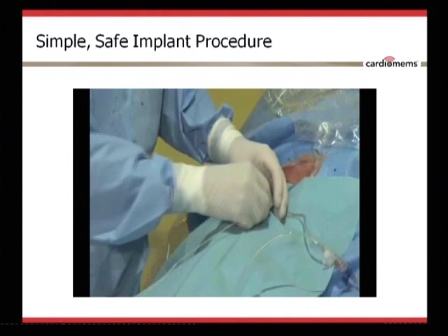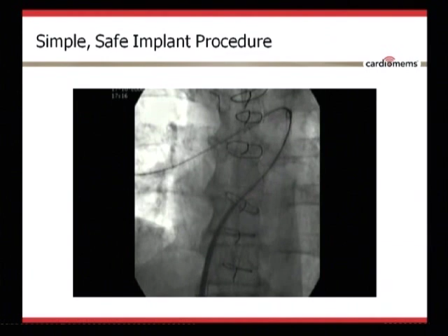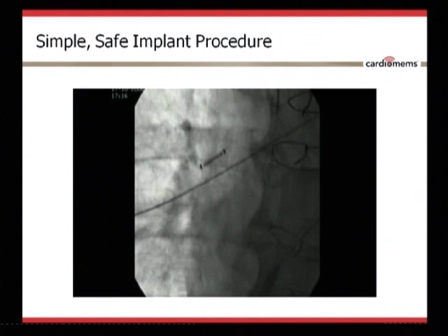The sensor is advanced through the sheath valve. Then it is advanced through the sheath and into the target deployment position. The sensor is released by pulling the tether wire, which threads through the catheter shaft and through the sensor. Okay, we saw the wires going up. After release, the delivery catheter and guide wire can be removed.